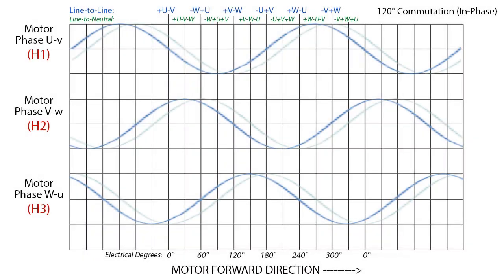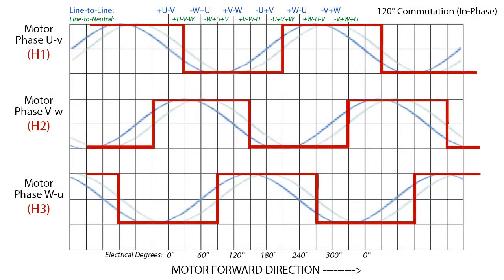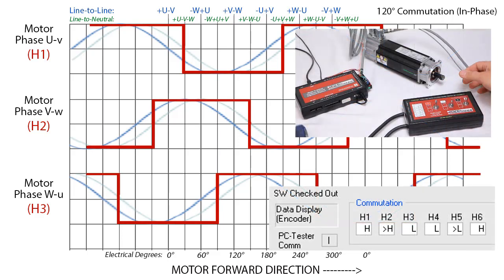Depending on the motor brand, some commutation signals are aligned to a line-to-neutral lockup, which uses all three switches. When we try the standard line-to-line lockup using only two switches, there's no toggle.